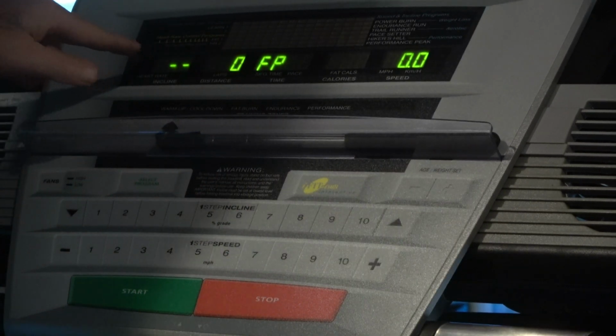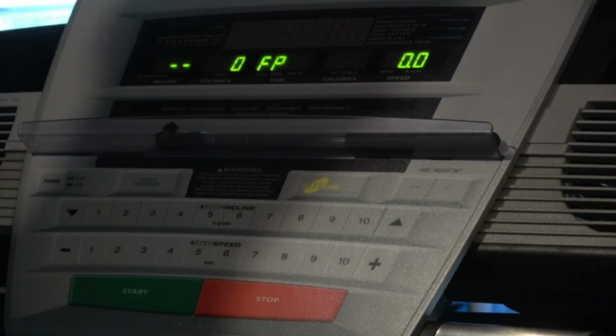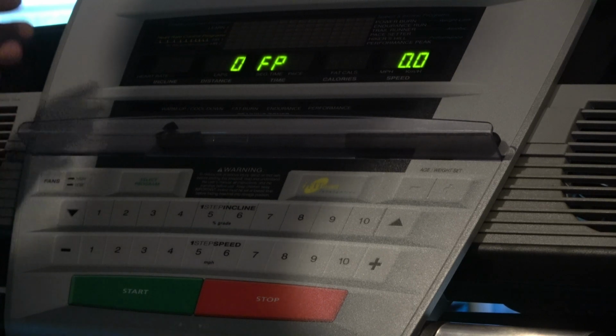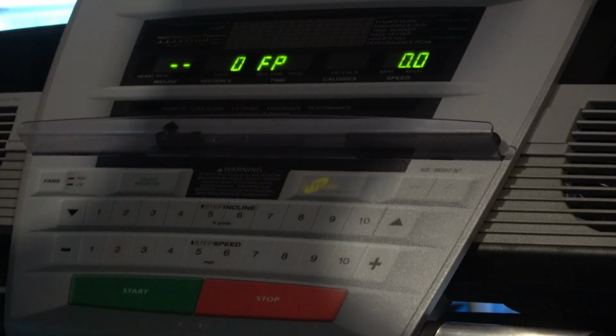So we get the two dots. The incline moves maybe 1 to 3 degrees, and that's it. So that means it's failed its calibration. We'll try and calibrate it again. So something's lost in the information side of it. It goes up 1 or 2 degrees, goes back down, and then stops.